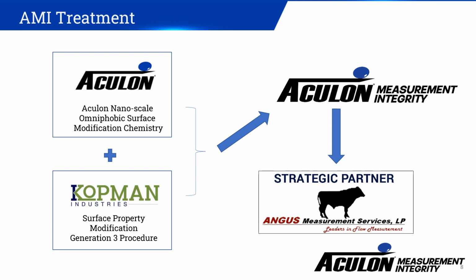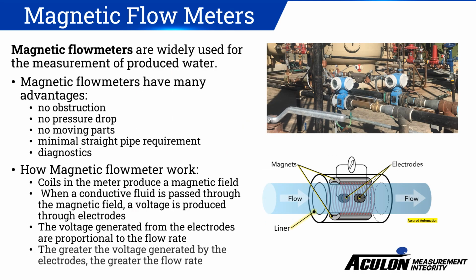Thank you, Steve. Magnetic flow meters are one of the preferred flow technologies used for the measurement of produced water. Magnetic flow meters have many advantages that include no obstruction of flow path, no pressure drop, no moving parts, minimal straight run requirements, and diagnostics that allow for both process integrity and meter health.